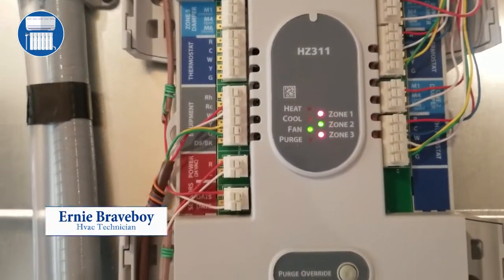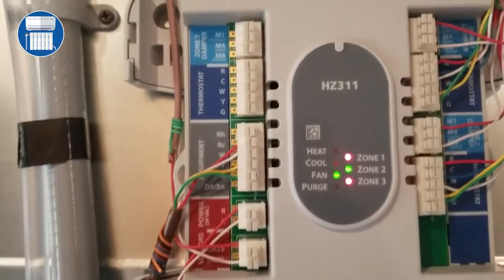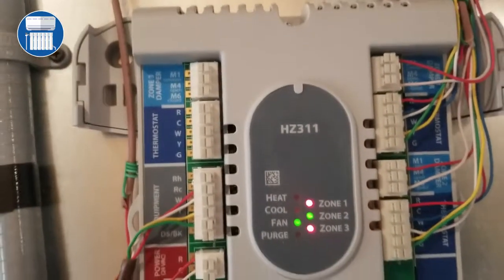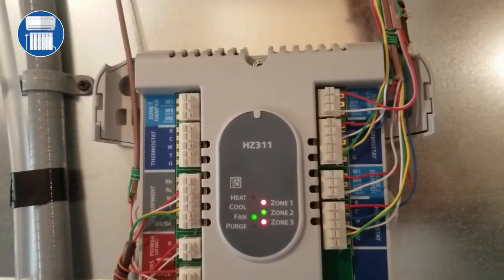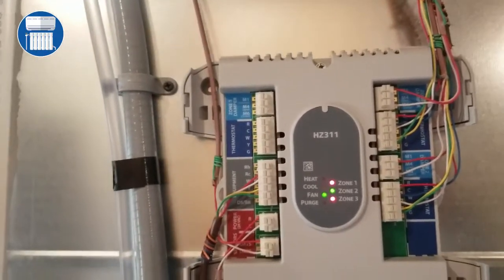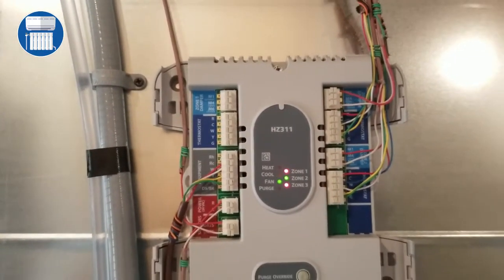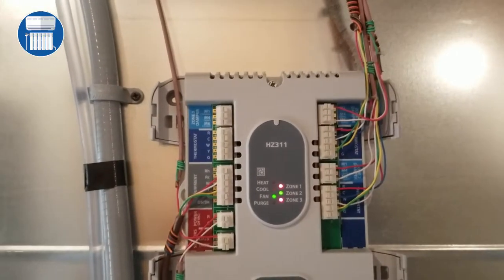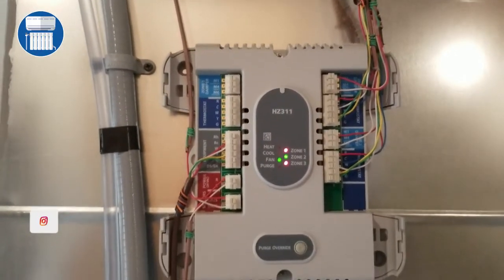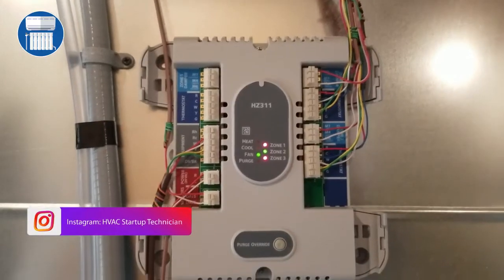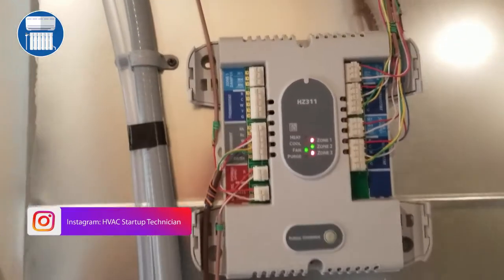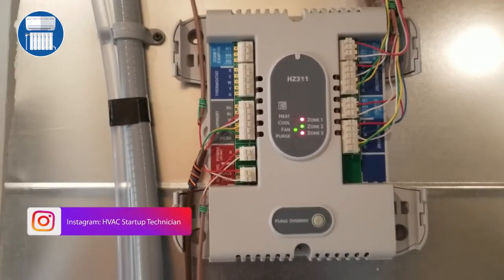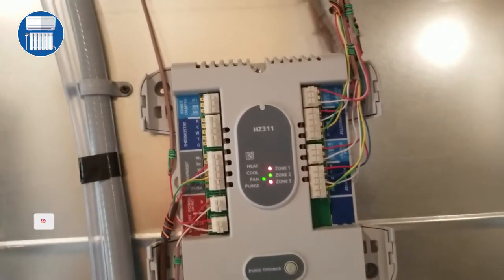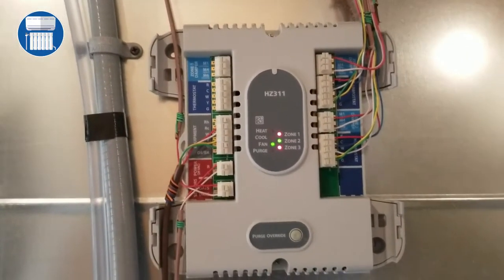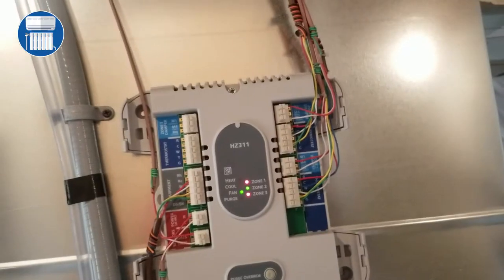This is a Honeywell HZ311 zone system. You can have two thermostats, one for each floor, and cut off upstairs for a minute or cut off downstairs, having one zone running or having them at different temperatures. If someone wants 65 upstairs and the person downstairs wants a higher temperature, you can do that too. I'll go through some of the steps as to how the zone system works.